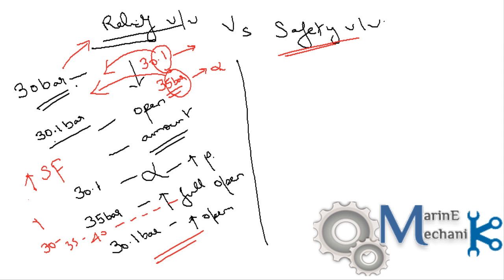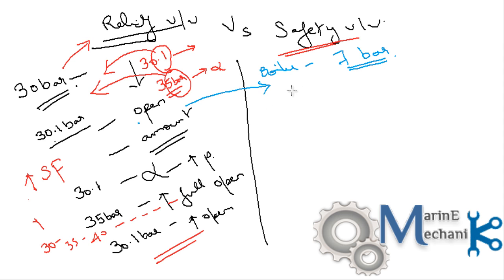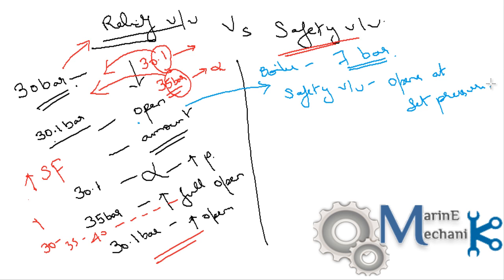Now let's look at the safety valve. Assume a boiler operating at 7 bar. Unlike the relief valve which opens slightly above the set pressure, the safety valve set at 7 bar opens at exactly 7 bar — it lifts at the set pressure.